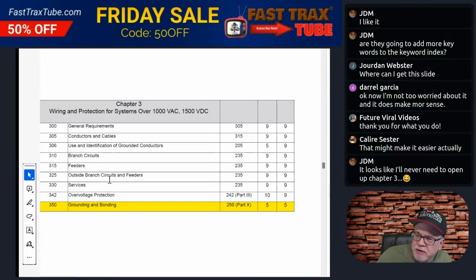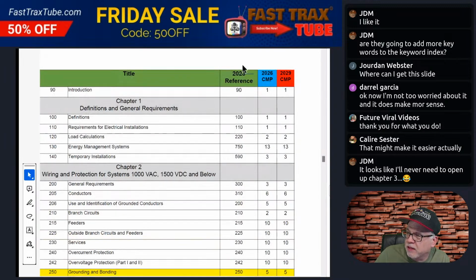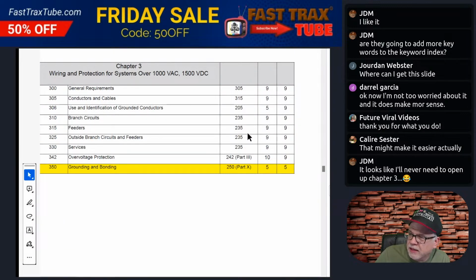Now look at here. Branch circuits, yes folks, over 1,000 volt AC branch circuits. Feeders from 235, it's going to be 315. For outside branch circuits and feeders, it's going to be 325. Services, which was 235 in the 2023, is now going to be 330. Over voltage protection, which was in 242 for over 1,000 volts, is going to be 342 now.